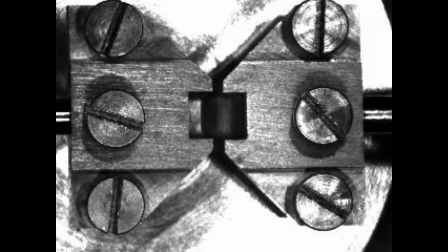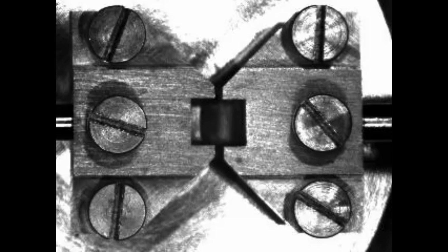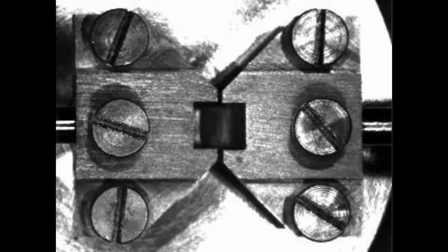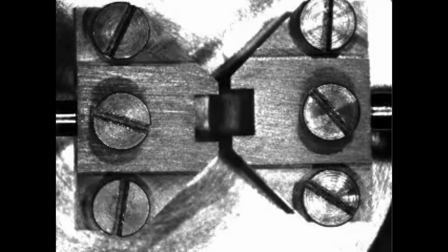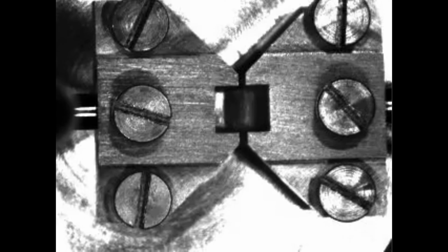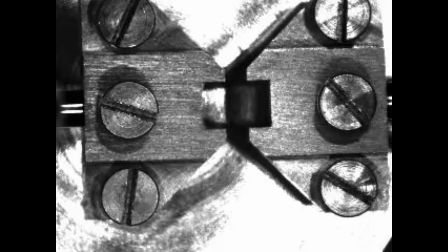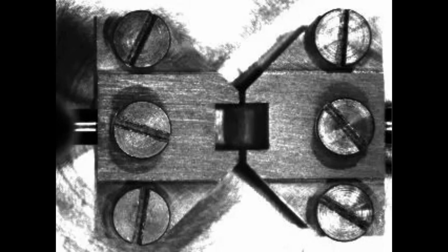Now gently move the jaws together and see how close your alignment is. We are still slightly off. We will make one more coarse adjustment. Although the jaws are aligned, you can see that the transducer side is higher than the positioner side. We will use 2 Allen keys to tighten the 2 back screws on the positioner side. This will raise the front of the jaw.